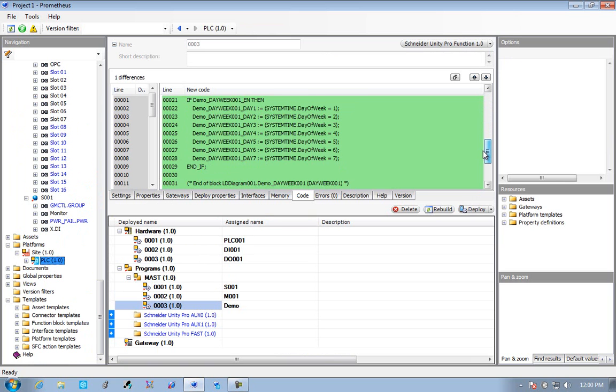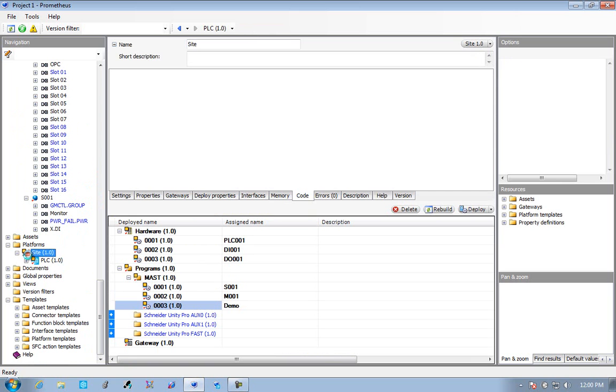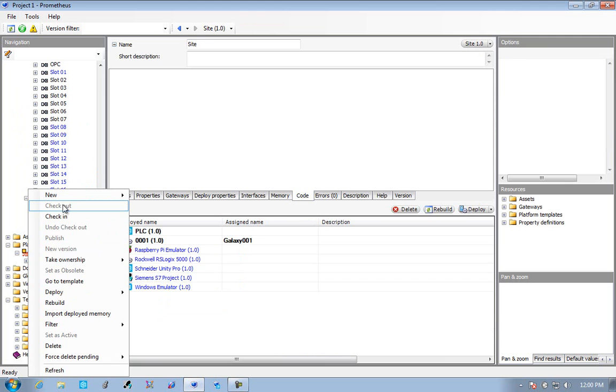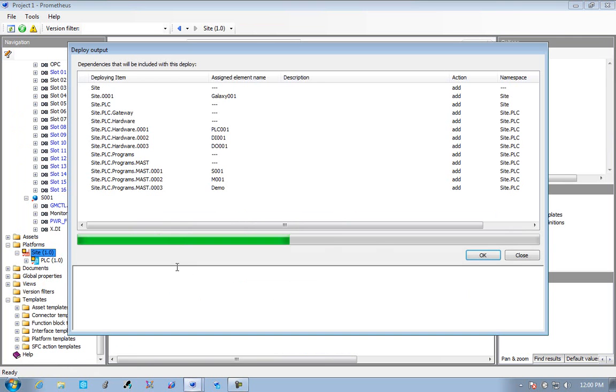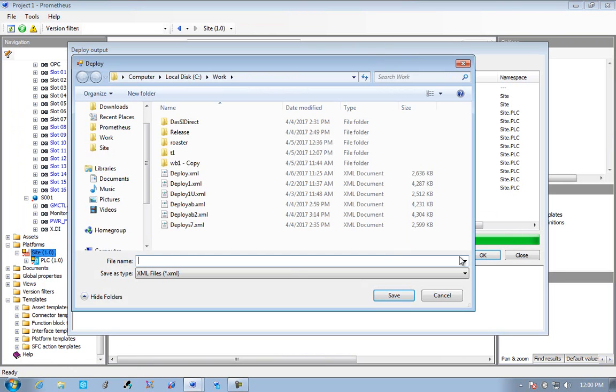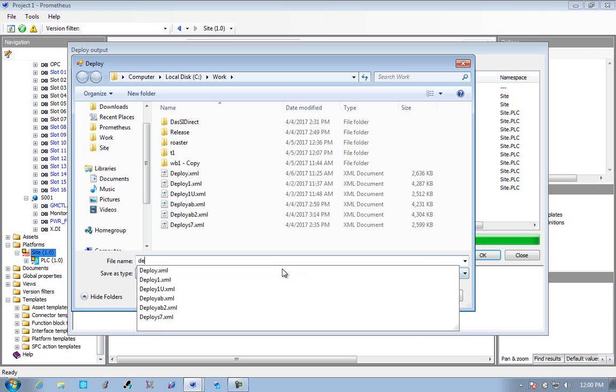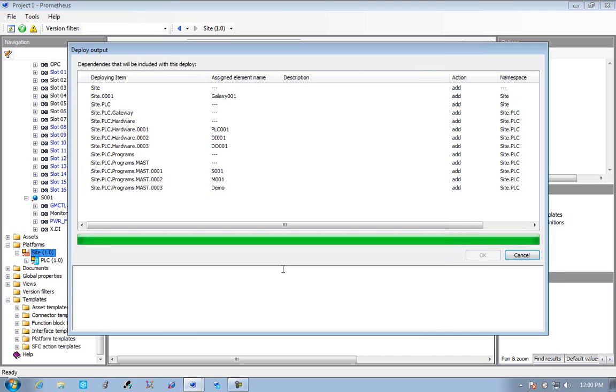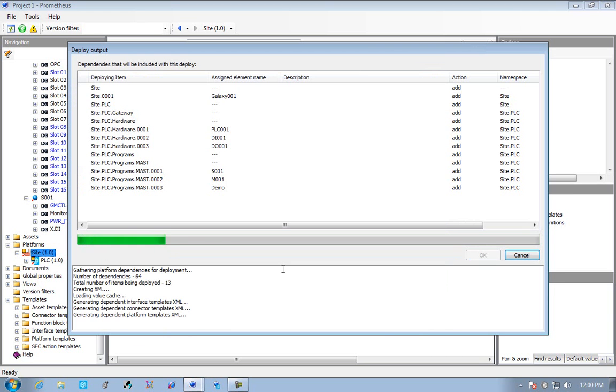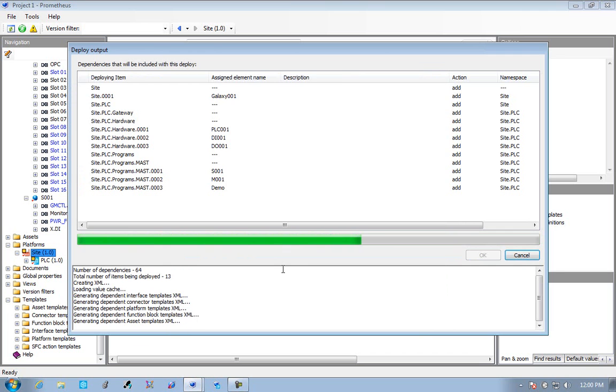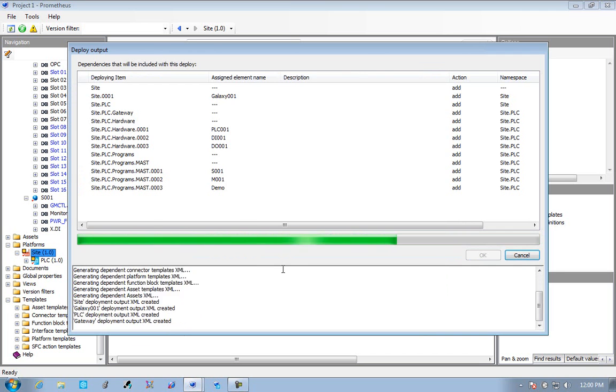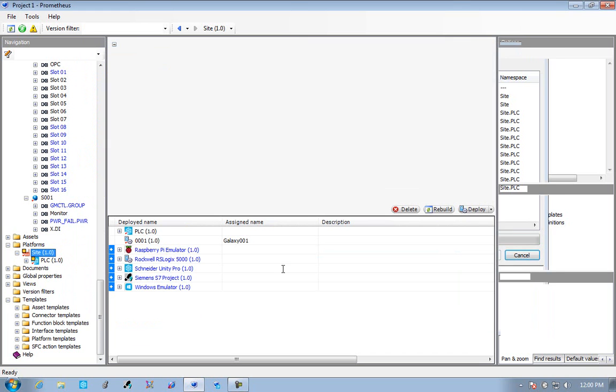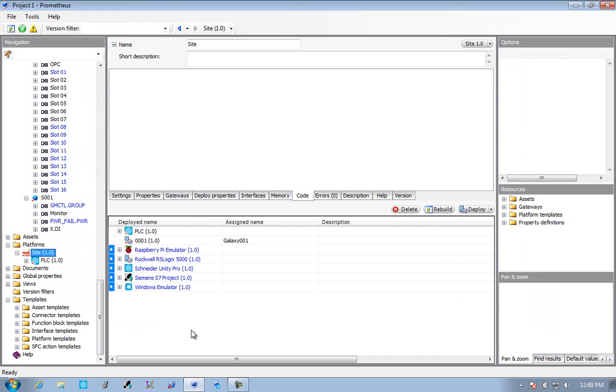That's where this logic came from that we've seen it's going to be deployed. Now we need to actually get the code into the controller. What we do is we deploy to an XML file. The XML file provides a support ability to actually now take this XML and execute it wherever the control software is, because we need to have access directly to the vendor's software, and it may not be on this machine.